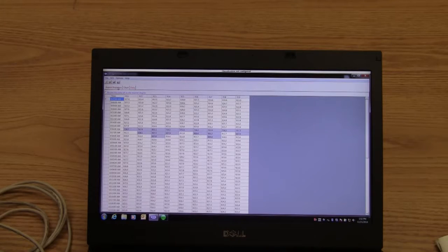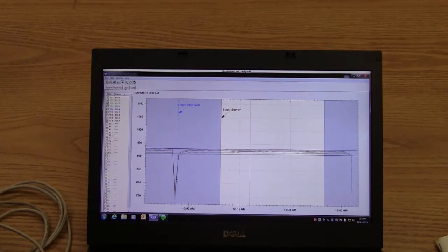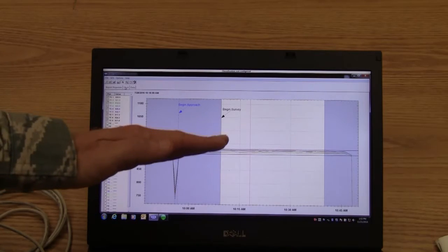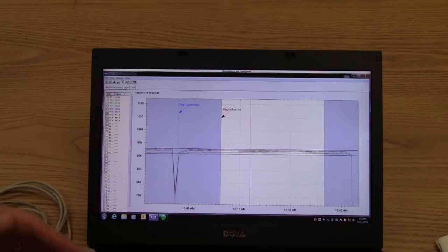I will say that I personally prefer the data because, like I said in video 1, numbers don't lie. This is accurate to 1/10 of a degree, and your chart is not as accurate. The scale of your chart or the resolution is not high enough to show you a deviation of 1/10 of a degree.